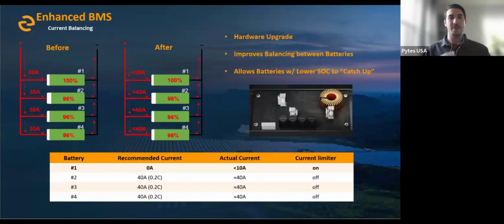charge. However, on the pack level, on the battery level, over time, you can see some variance between parallel connected batteries, right? That can be due to small manufacturing differences, differences in resistance, differences in your cabling or busing. That's why it's important to have the same length, same gauge cables between all your batteries in the common bus. So over time, if you do have batteries that become out of balance, like maybe one's at 99 or 98%, some others are at 96.